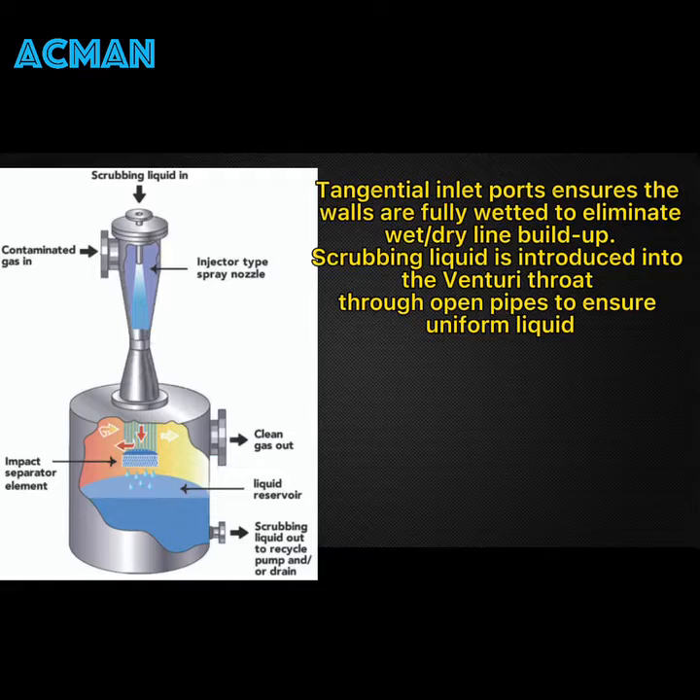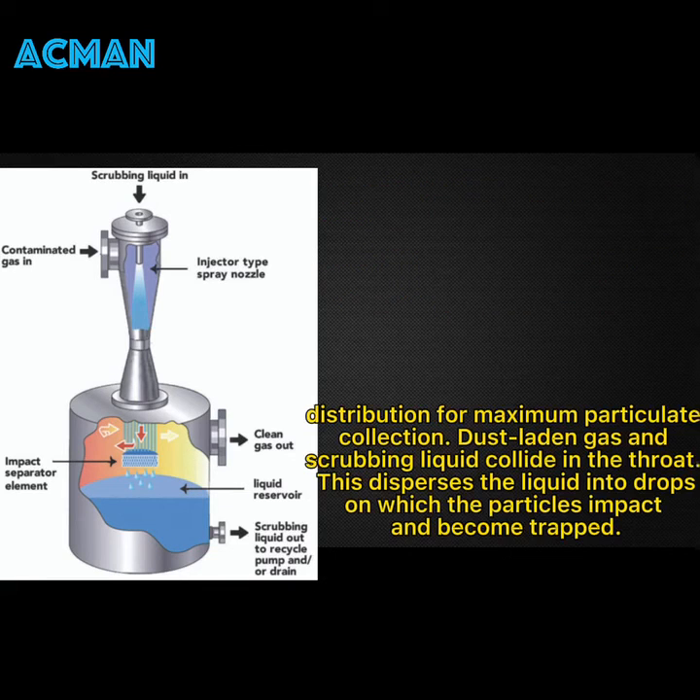Tangential inlet ports ensure the walls are fully wetted to eliminate wet-dry line buildup. Scrubbing liquid is introduced into the Venturi throat through open pipes to ensure uniform liquid distribution for maximum particulate collection.